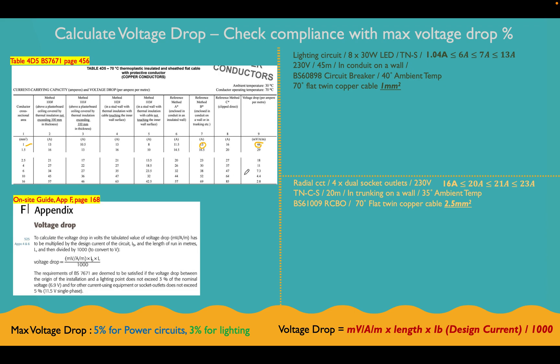Now let's do the second one. So for the second circuit, we went down and we needed a cable that could take at least 21 amps, so we chose 23 here, went across, and that meant we were selecting a 2.5mm cable. And then same situation again, keep scrolling to the last column, which is voltage drop per ampere per meter. And then if we look, we get a value of 18. So we're going to select these values in a minute and go and put these into the formula.